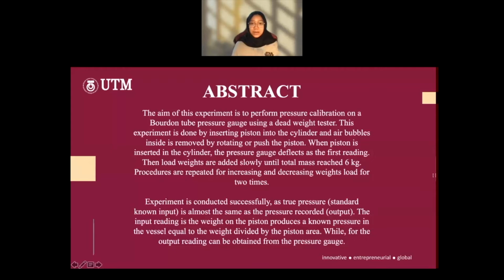Assalamualaikum and hello everyone. Now I will explain the abstract. The aim of the experiment is to perform pressure calibration on a Bourdon tube pressure gauge using a dead weight tester. The experiment is done by inserting the piston into the cylinder, and air bubbles inside are removed by rotating or pushing the piston. When the piston is inserted in the cylinder, the pressure gauge deflects as the first reading. Then, load weights are added slowly until the total mass reaches 6 kg. The procedure is repeated for increasing and decreasing weight load 2 times. The experiment is conducted successfully as the true pressure is almost the same as the pressure recorded.